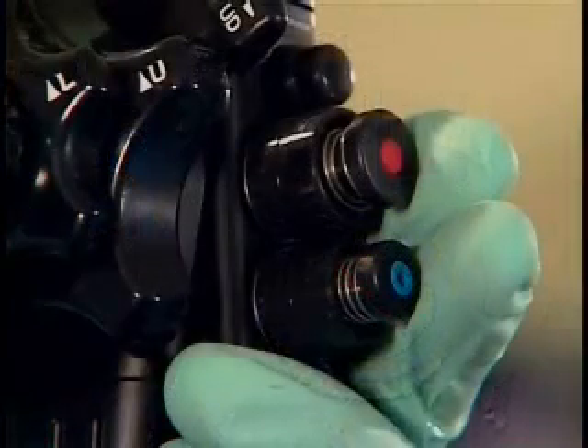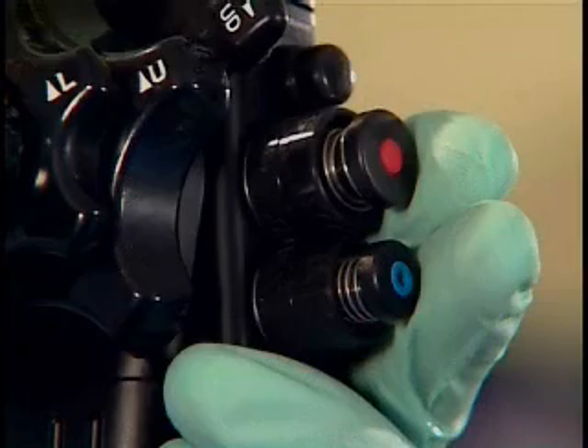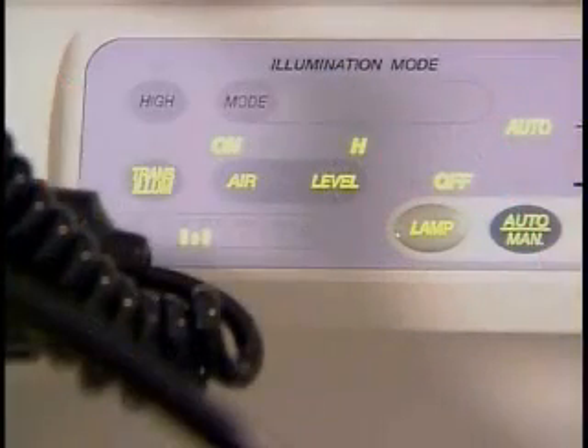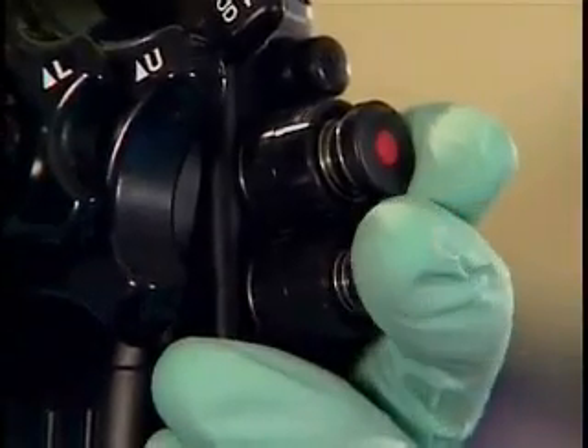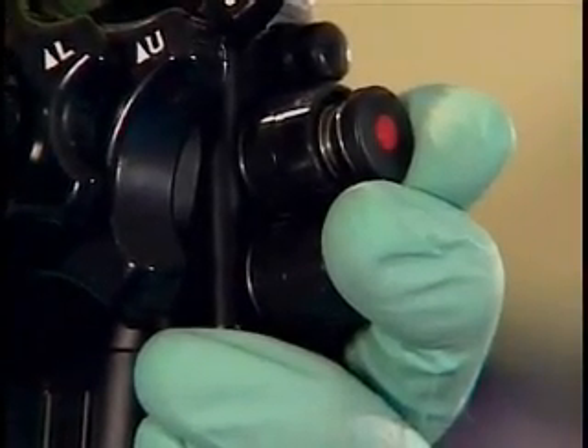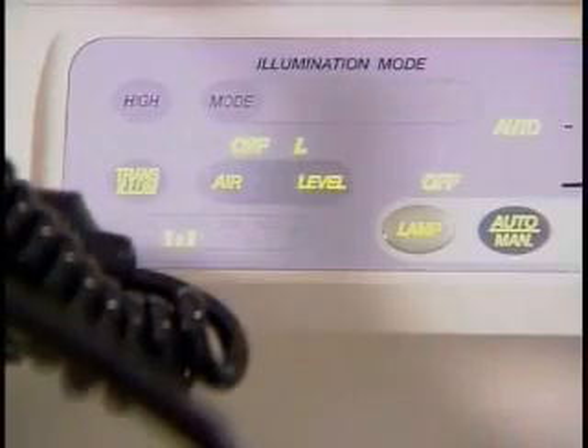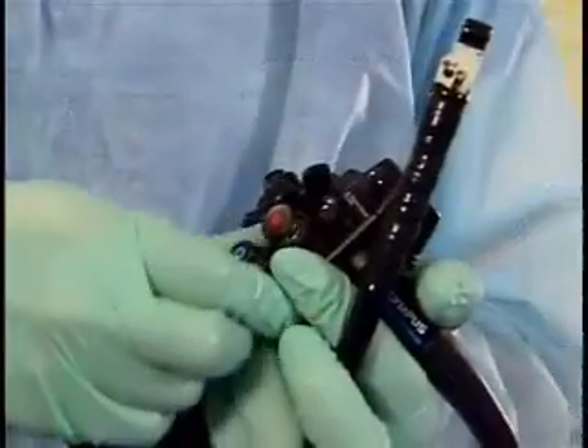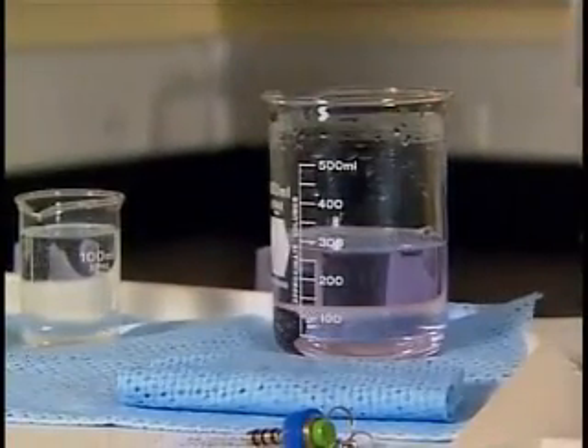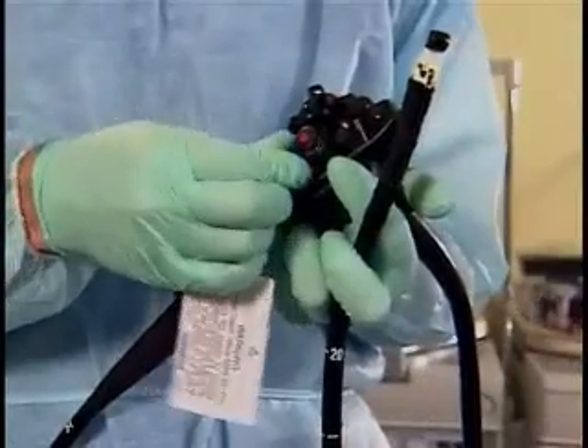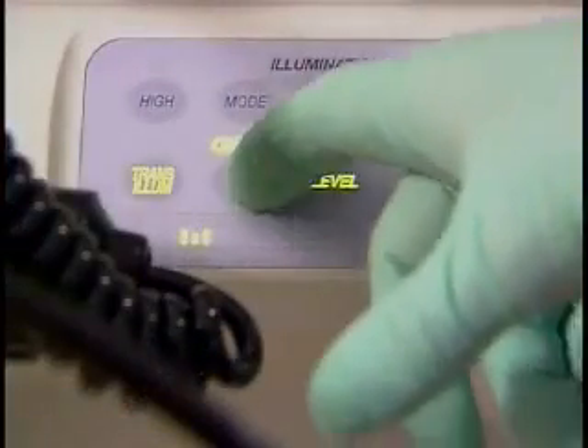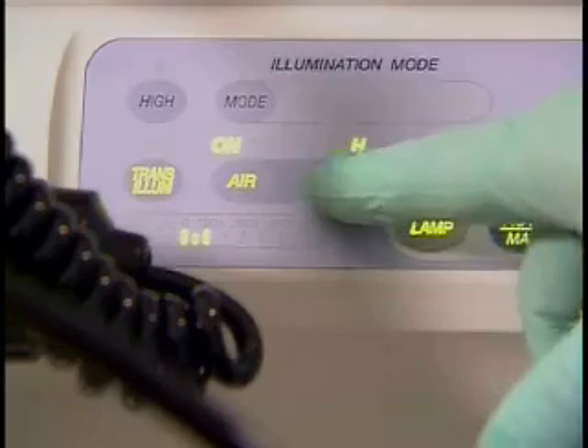Next, we will flush water and air into the air, water, and balloon channels. Confirm the light source is on, and then depress the air-water valve completely to feed water into the balloon channel. Turn off the airflow regulator on the light source. Then, remove the air-water valve and place it in detergent solution. Attach the air-water channel cleaning adapter. Turn on the light source and switch the airflow regulator to maximum output.